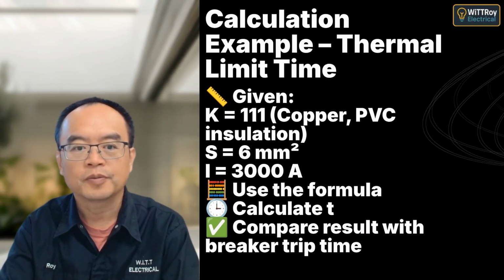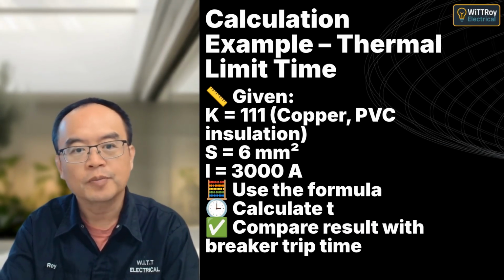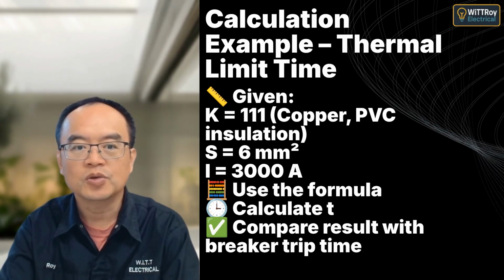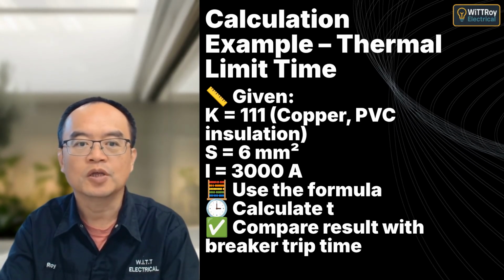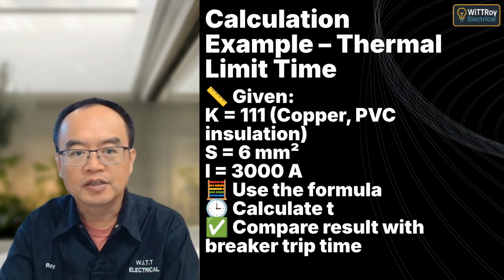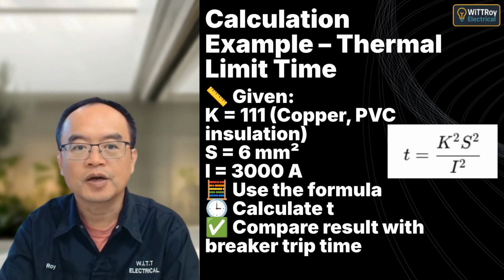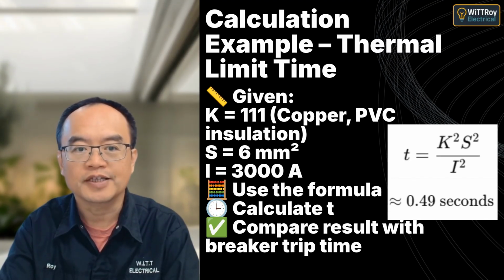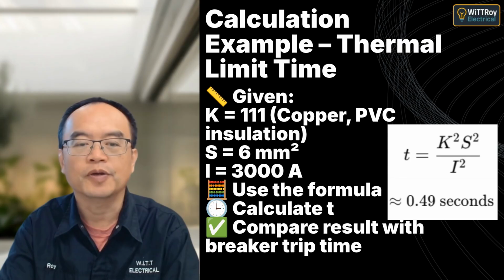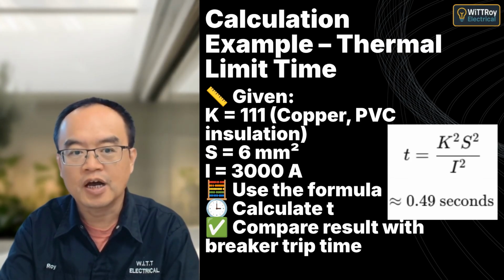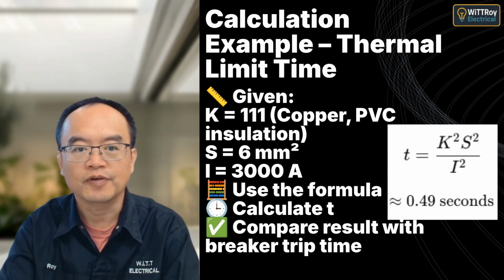Let's work through an example using the short circuit thermal limit formula. Say we've got a 6 square millimeters copper cable, K is 111 and fault current is 3000 amps. Plug it into the formula, the result is about 0.49 seconds. That means the circuit breaker or fuse must trip in less than half a second to stop the cable from overheating. Great effort, everyone. Understanding prospective short circuit currents helps maintain electrical safety. Let's reinforce our learning with some Moodle questions next.